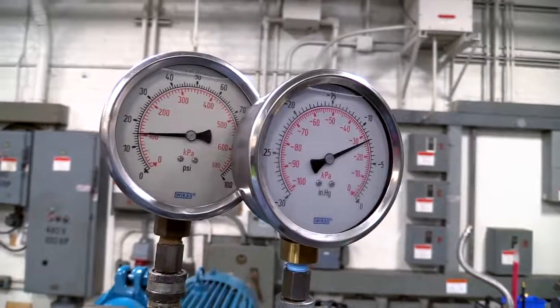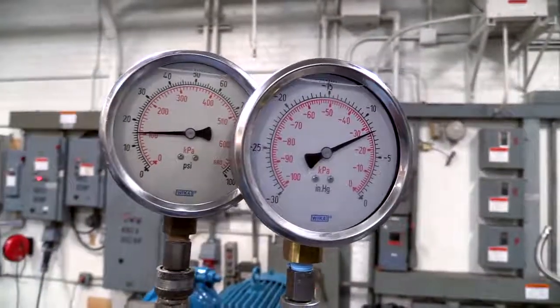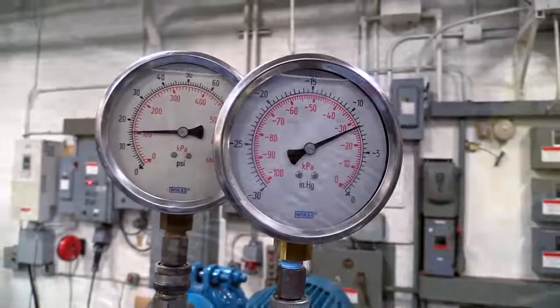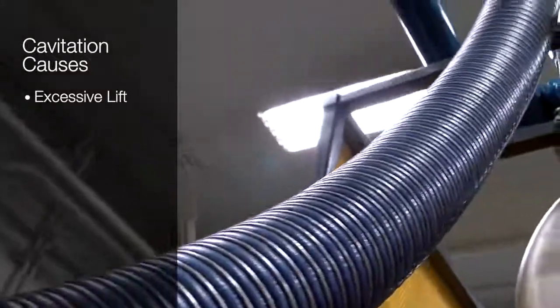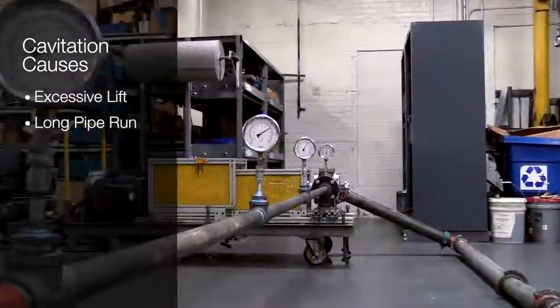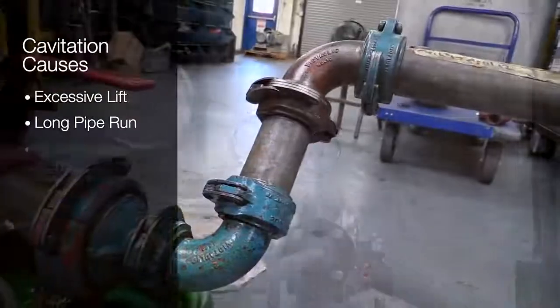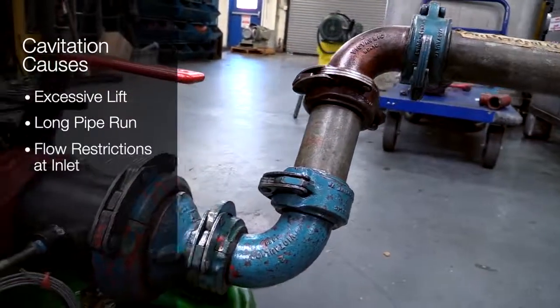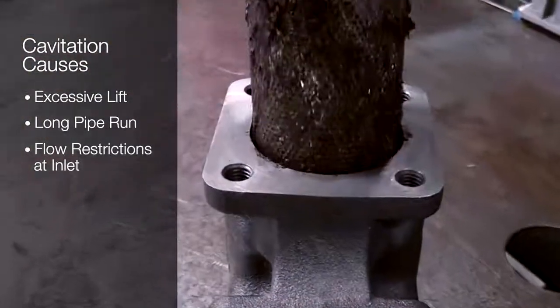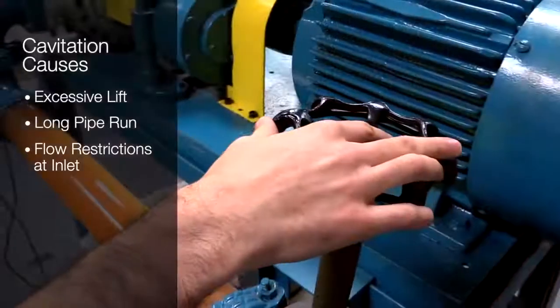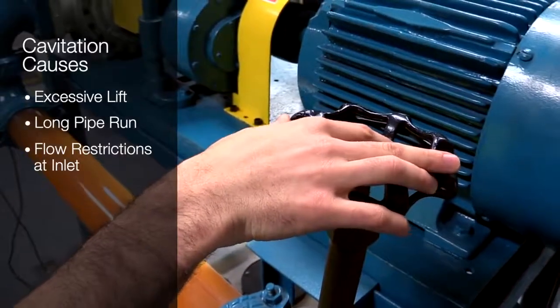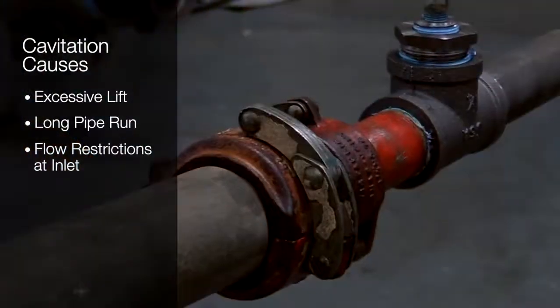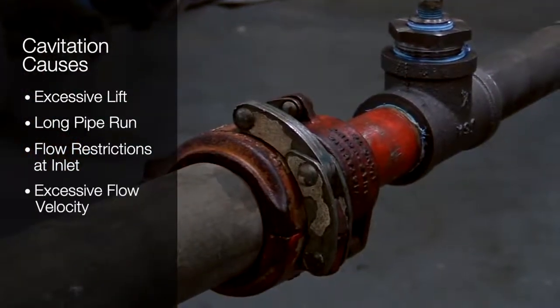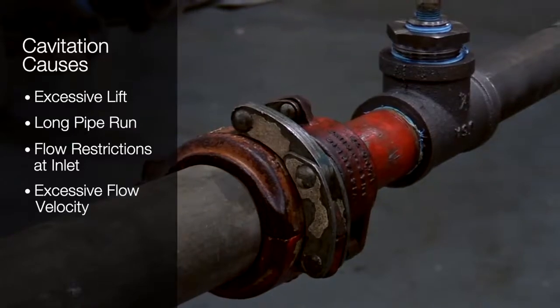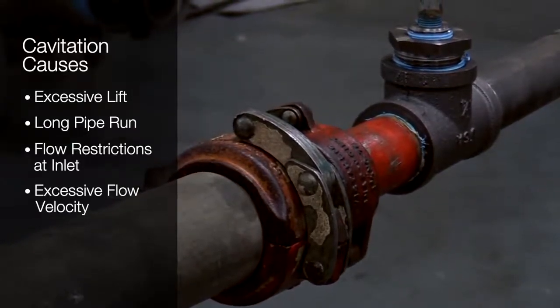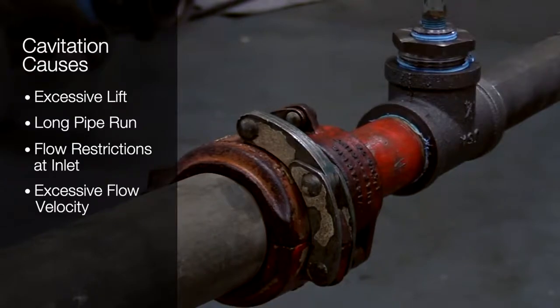Vapor forms when liquid pressure drops below vapor pressure. There are many potential causes: excessive lift, long suction piping, flow restrictions near the inlet, such as a pipe elbow, a clogged strainer, or when a valve is constricting flow, or where there is excessive flow velocity, which can be caused by undersized piping. These elements combine to reduce the system's NPSH available.